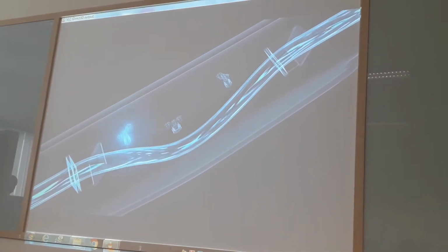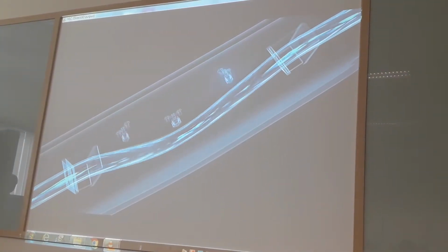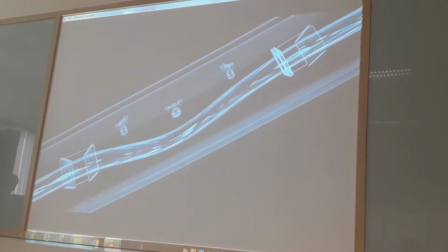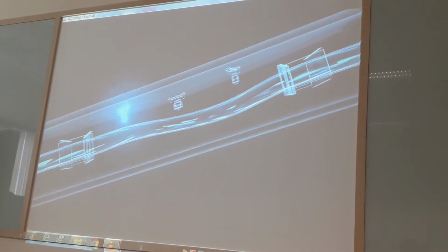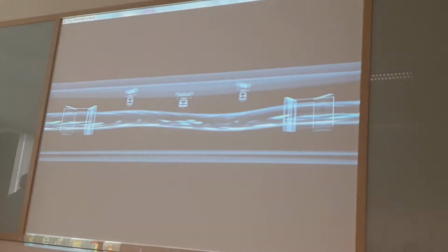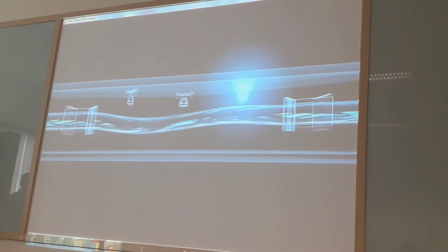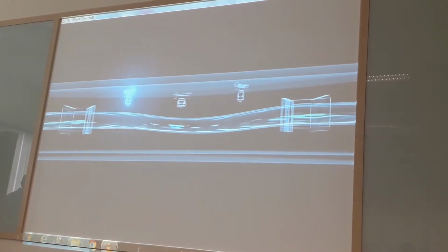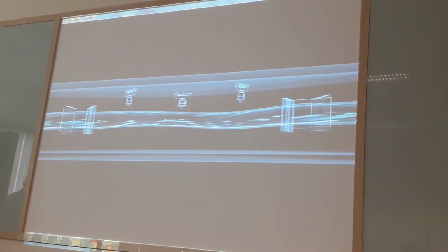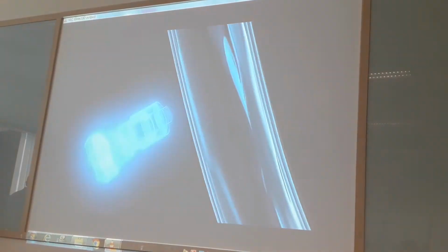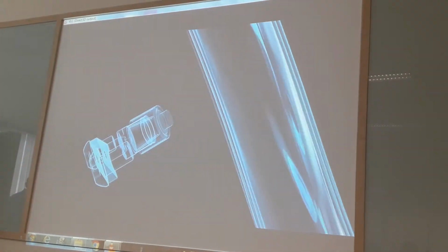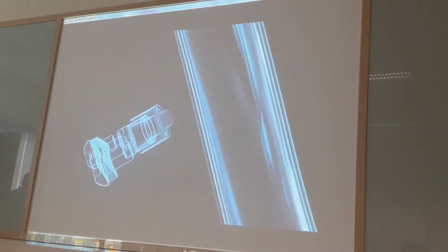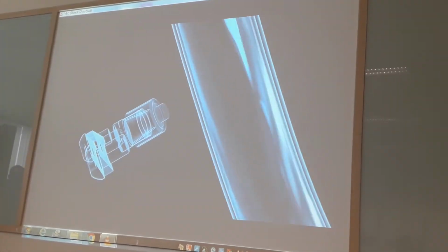As soon as the fluid starts to flow in the measuring tube, however, additional twisting is imposed on the tube's uniform oscillation, a result of the liquid's inertia. Now, due to the Coriolis effect, the inlet and outlet sections of the tube oscillate in different directions at the same time. The highly sensitive sensors pick up this change in the tube oscillation in terms of time and space.